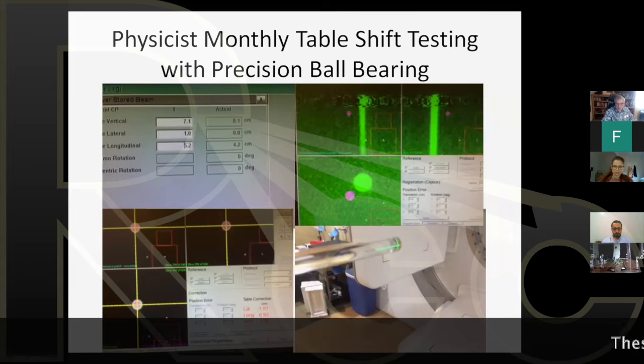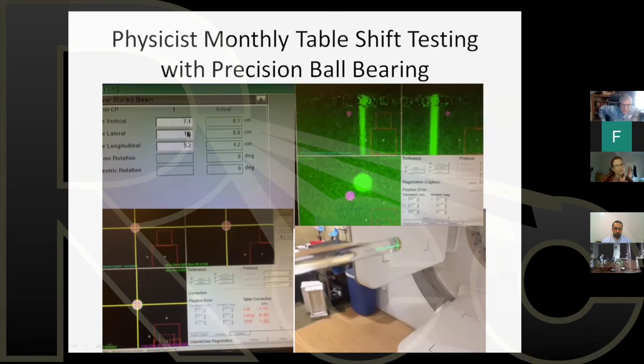Another thing you do with this test, at least what I do, is once a month, I also check the accuracy of the table shifts. So I will take the BB and I will offset it, usually a centimeter in each direction. Like here, I took the table and I dropped the table down by a centimeter. And then I moved the table left and right, left to the left a centimeter. And then I moved it in and out by a centimeter. And then I re-cone beam CT.